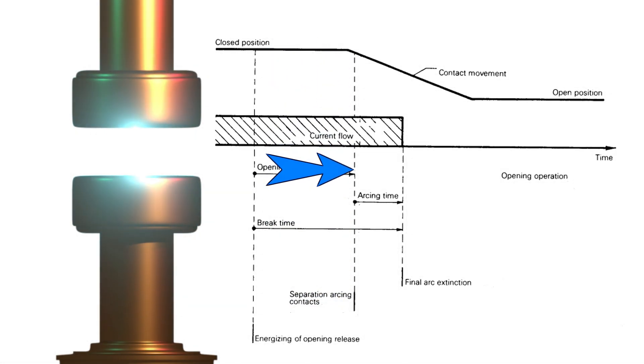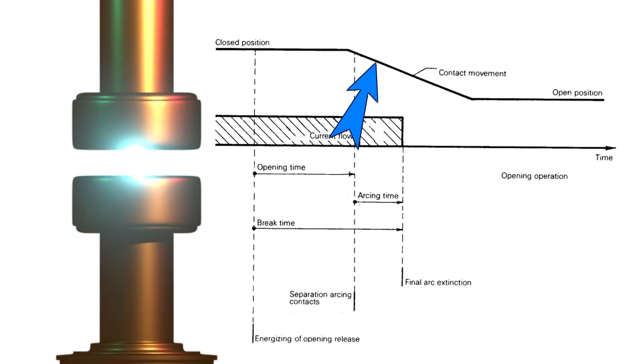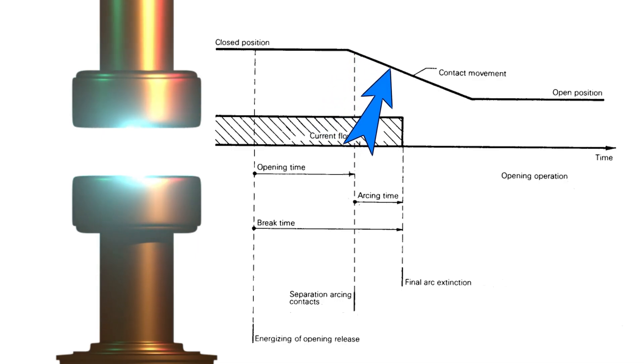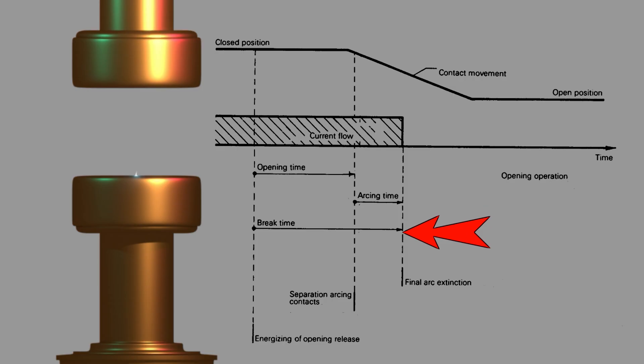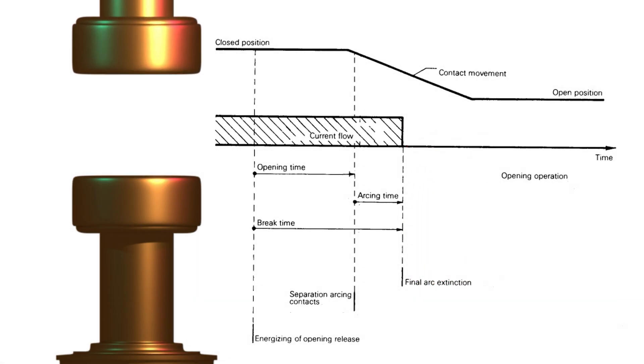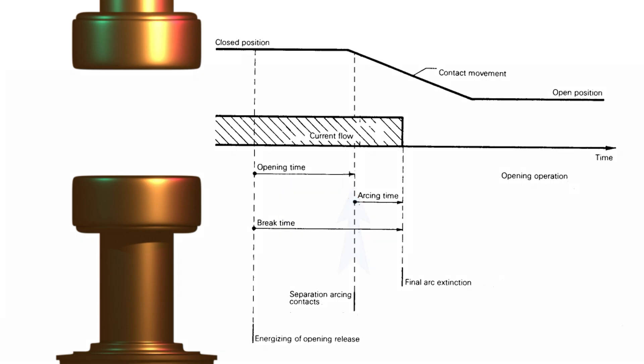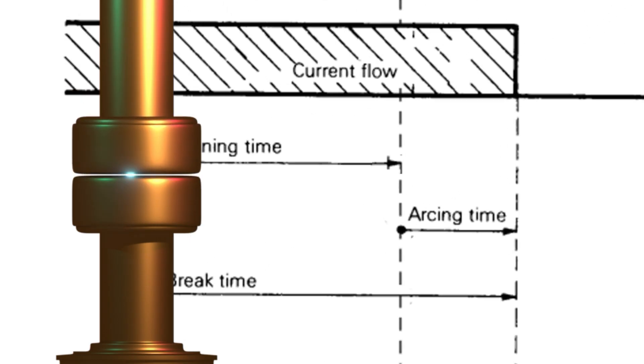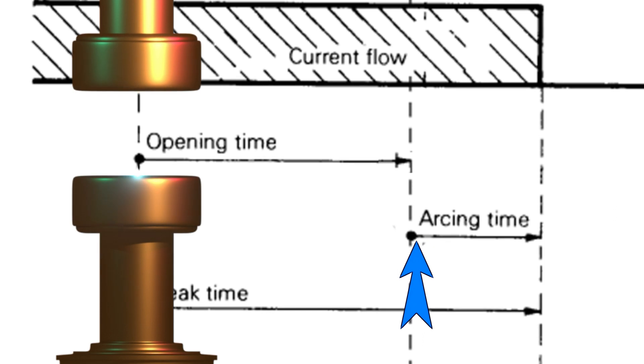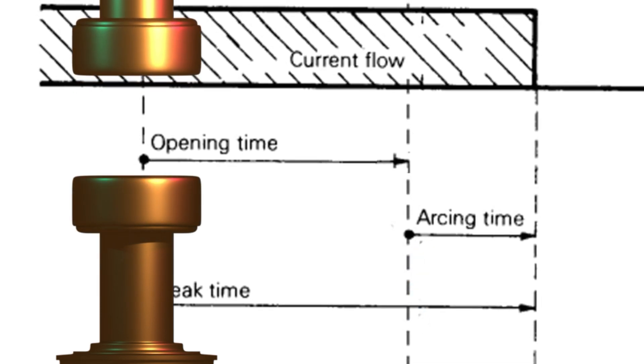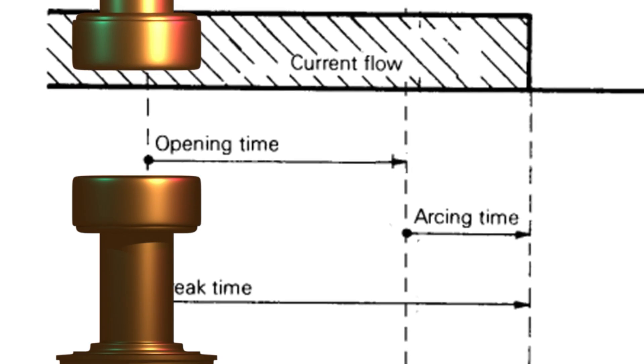After physical separation, the contact is still moving backward from the fixed contact and the contact gap is increasing. This inclined line indicates the movement of the moving contact away from the fixed contact. After a certain distance, say at that instant, the arc finally extinguishes — that means the current is finally interrupted. So this is the opening time, which means the time between energizing the opening release and the physical separation of the contacts. And this is the arcing time, which is initiated as soon as the moving contact gets separated from the fixed contact and the arc starts, to the final instant when the arc is finally extinguished.